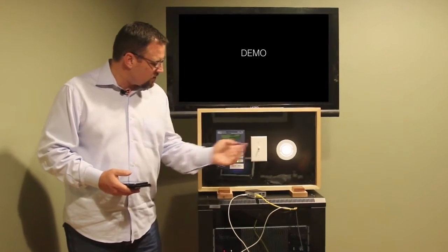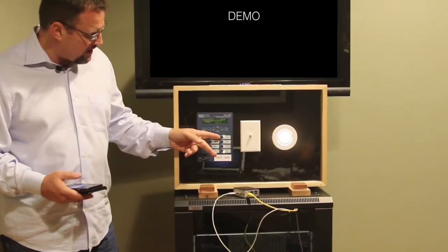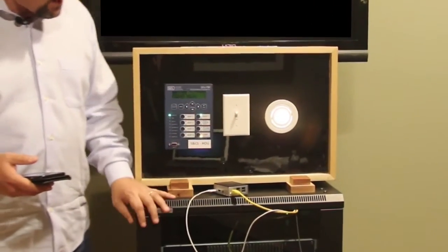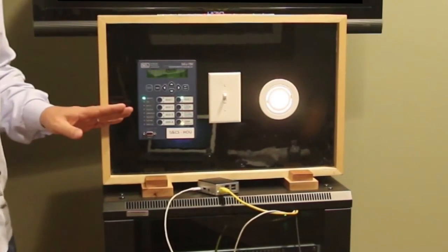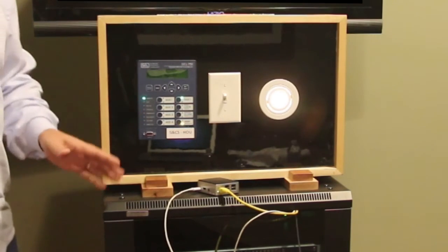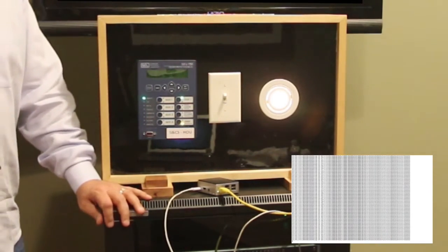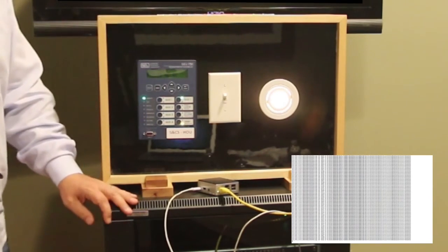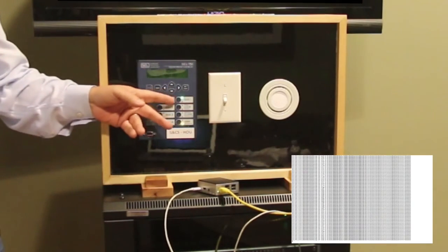So what I'm going to do now is turn on the power. You'll notice that the indicator turned to green, and the RTAC is transmitting that the power is good. And now I have Sam sitting off screen, and he's going to launch an attack right now against this substation. I'll give him just a second to launch it. And as soon as he does that, I can turn the light off. And look, the power is still indicating that it's on with this green indicator.